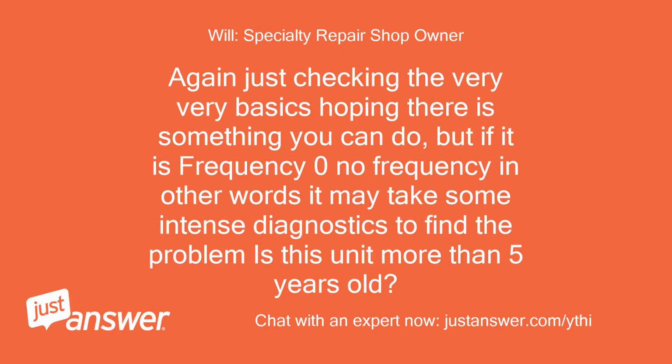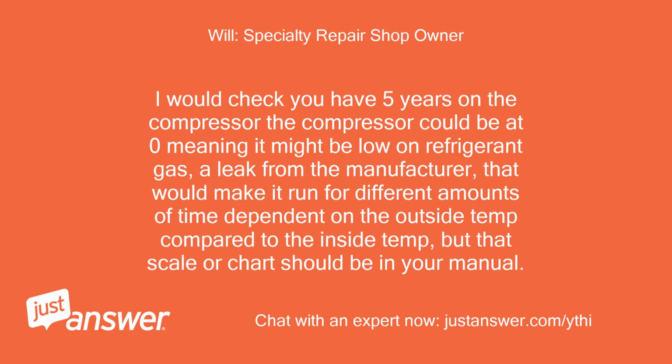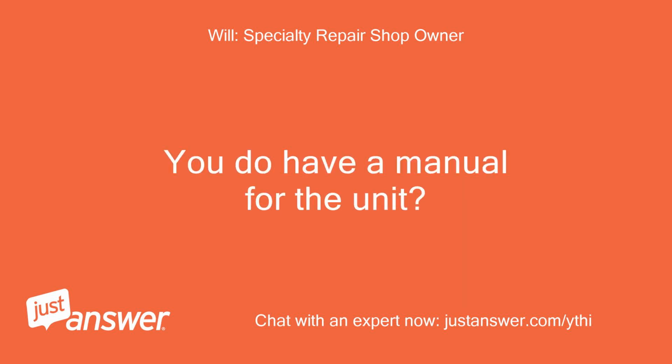Is this unit more than 5 years old? I would check the 5-year warranty on the compressor. The compressor could be at 0, meaning it might be low on refrigerant gas, a leak from the manufacturer, that would make it run for different amounts of time dependent on the outside temp compared to the inside temp, but that scale or chart should be in your manual. You do have a manual for the unit?